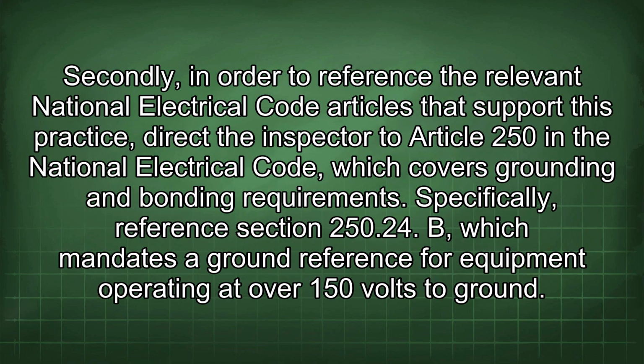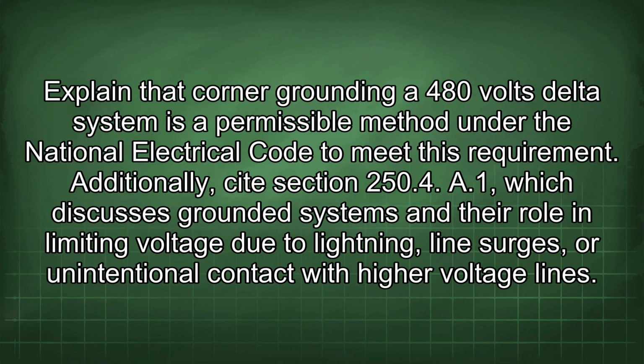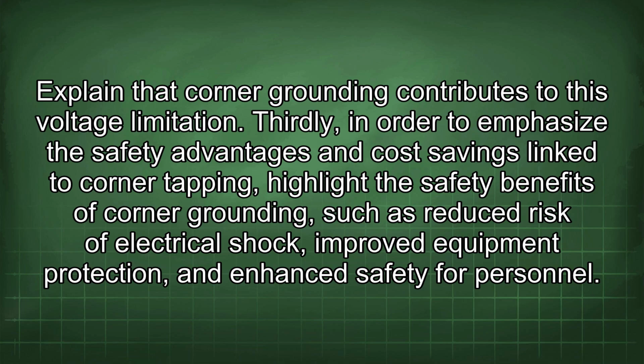Secondly, in order to reference the relevant National Electrical Code articles that support this practice, direct the inspector to Article 250 in the National Electrical Code, which covers grounding and bonding requirements. Specifically, reference Section 250.24(b), which mandates a ground reference for equipment operating at over 150 volts to ground. Explain that corner grounding a 480-volt delta system is a permissible method under the National Electrical Code to meet this requirement. Additionally, cite Section 250.4(A)(1), which discusses grounded systems and their role in limiting voltage due to lightning, line surges, or unintentional contact with higher voltage lines. Explain that corner grounding contributes to this voltage limitation.